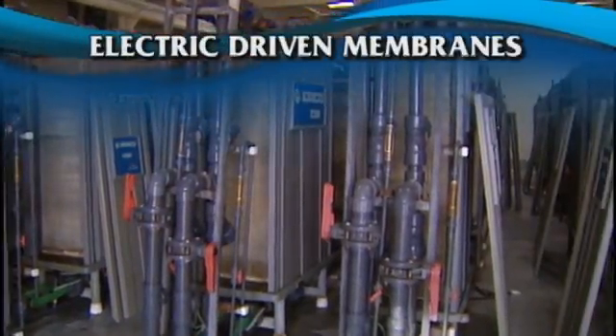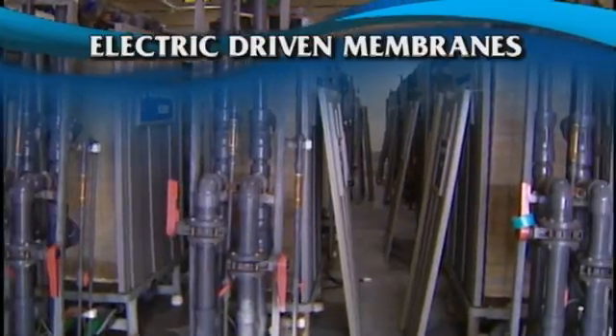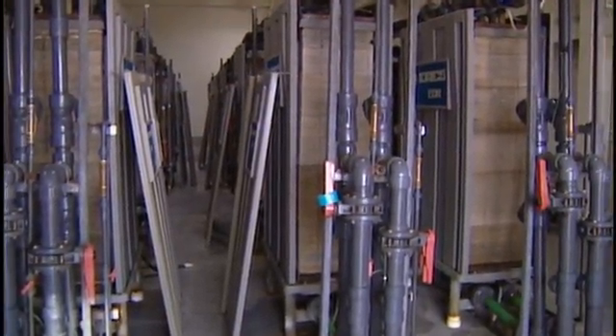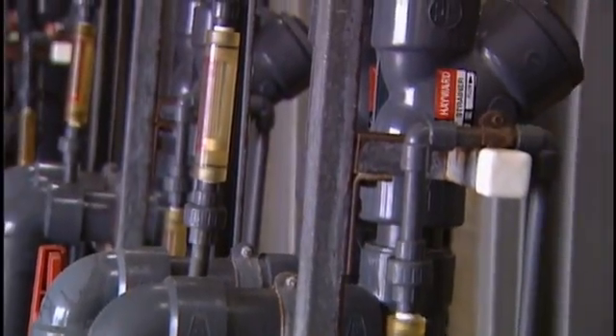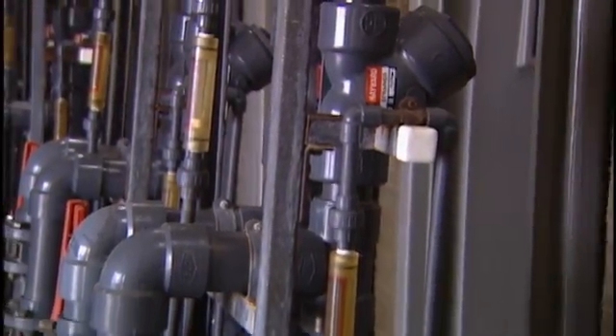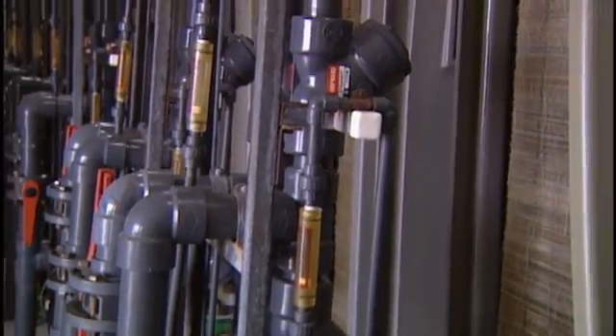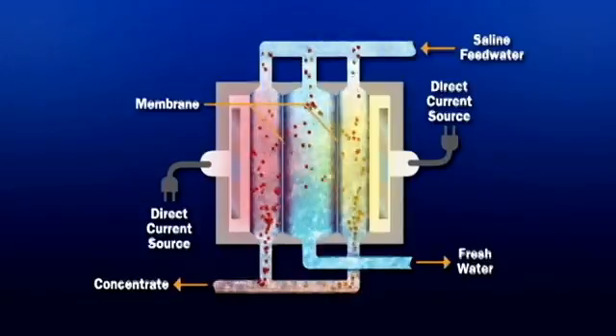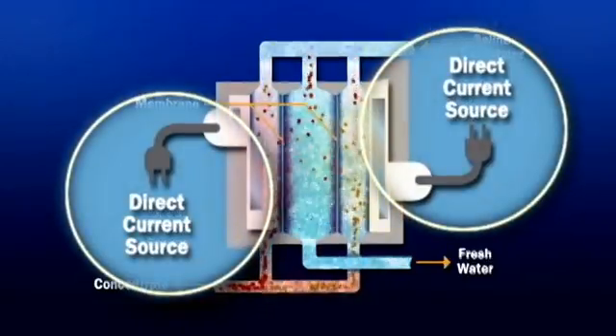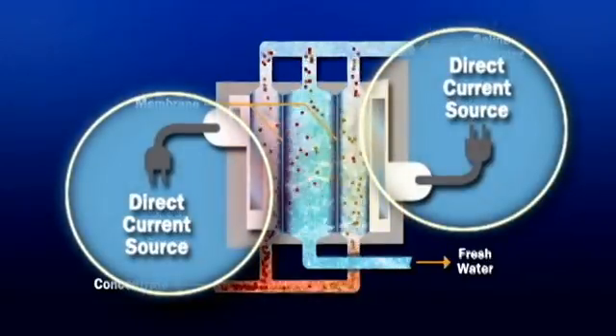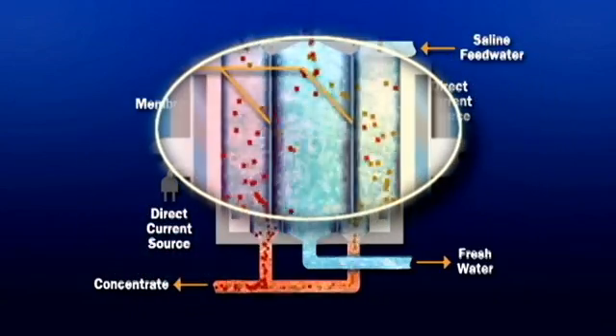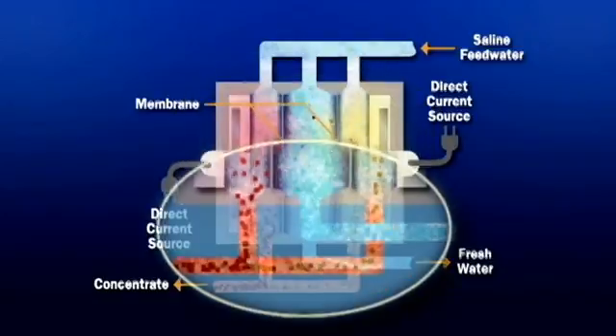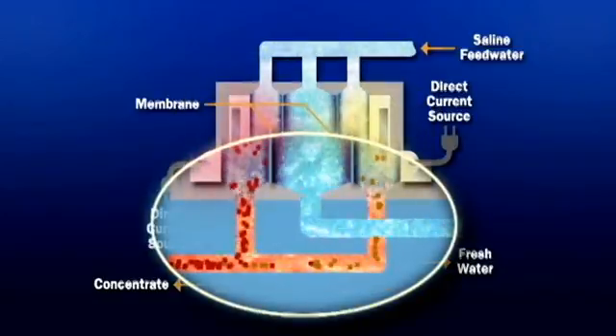Electric-driven membranes purify water by moving ions across a membrane using an electric current. They are used in electrodialysis, or ED, and electrodialysis reversal, or EDR. In ED, ions are transferred through a membrane as a result of a direct electric current applied to the solution. The current carries ions through the membrane from the less concentrated solution to the more concentrated one, and the high concentrations are then removed.